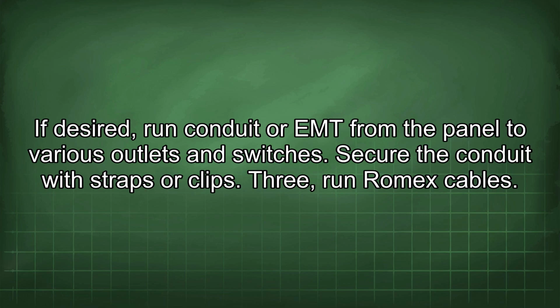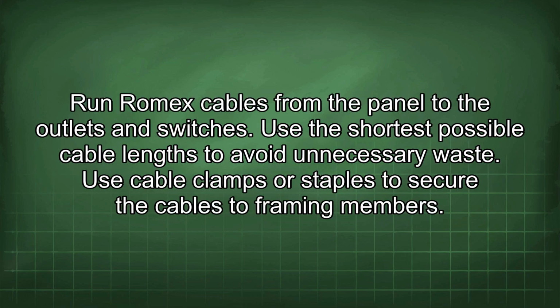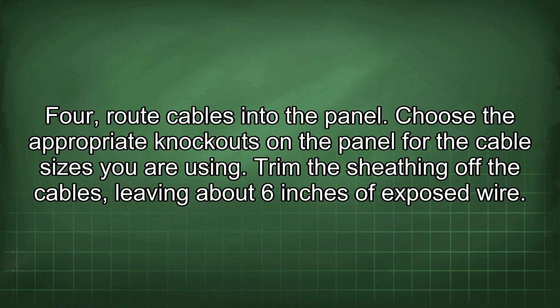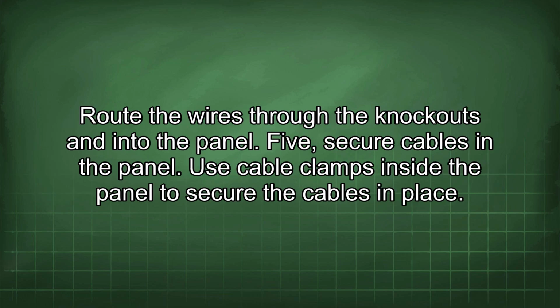3. Run Romex cables. Run Romex cables from the panel to the outlets and switches. Use the shortest possible cable lengths to avoid unnecessary waste. Use cable clamps or staples to secure the cables to framing members. 4. Route cables into the panel. Choose the appropriate knockouts on the panel for the cable sizes you are using. Trim the sheathing off the cables, leaving about 6 inches of exposed wire. Route the wires through the knockouts and into the panel.